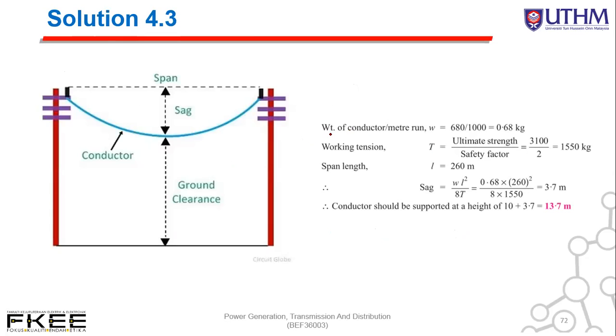Weight of conductor per meter run, okay, W is 680 over 1000, we got 0.68 kg. Okay. Working tension T, okay, ultimate strength divided by safety factor. So ultimate strength is 3100, safety factor is 2, so we got T equal to 1550 kg. The span length is 260 meter. So directly we use all these values, put in the formula of sag. So we got the sag value is 3.7 meter. And then the conductor should be supported at a height of 10 plus 3.7 equal to 13.7 meter.